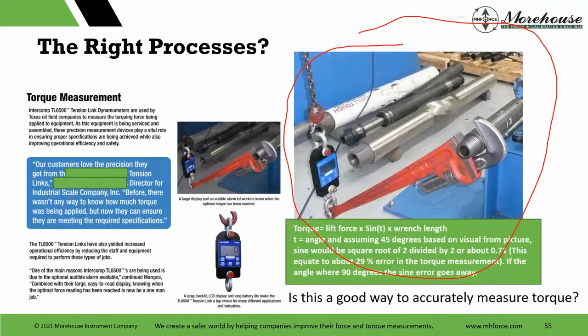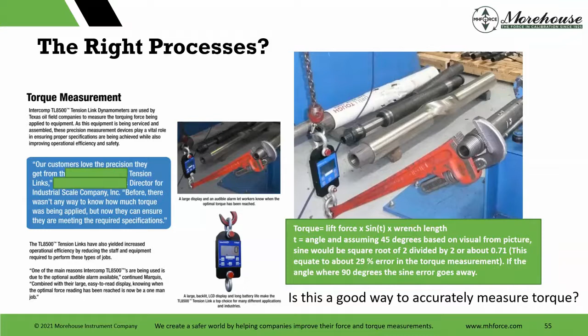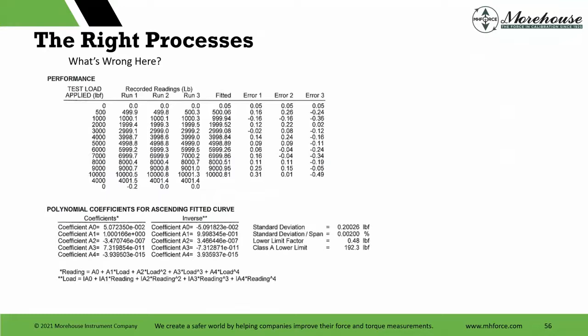But if we look at it, simple calculation, simple math on this. This is where marketing doesn't understand metrology, and maybe other people don't understand metrology too. But if you just look at what torque is, and you look at this angle, if that's 45 degrees, some might argue it's not 45, but that's minutia. But apply the formula at 45 degrees. That picture right there, I estimate, is showing at least 29% error. If they changed it to 90 degrees, that one piece of the error goes away. That's an active document, still on the website, still trying to sell that product as a good way to measure torque. So what's wrong here?